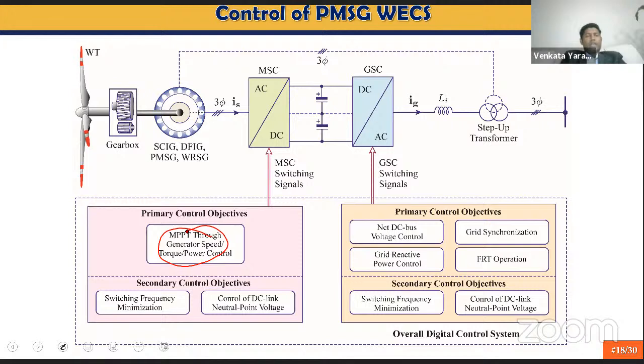Secondary control objectives are, for example, that I need to reduce the switching frequency because we are talking about megawatt level applications. In order to decrease the losses, we need to decrease the switching frequency. And if I have back-to-back connected neutral point clamped converters, I also need to control the neutral point voltage.